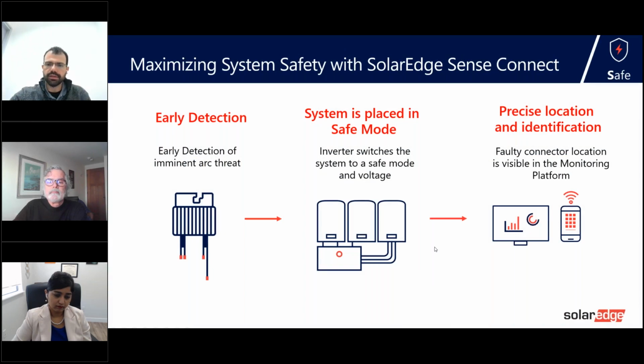Moving on, that's a summary of what we do. We detect early issues with the connectors. As soon as that's detected, the system is placed into safe mode. We not only turn off the inverter, but all of the optimizers are brought to 1 volt DC at their output, so string level is about 30 volts DC. So you're de-risking any issues if there is a problem there. Then we send a warning to the monitoring platform to let the operation and maintenance team know where to look for the issue.